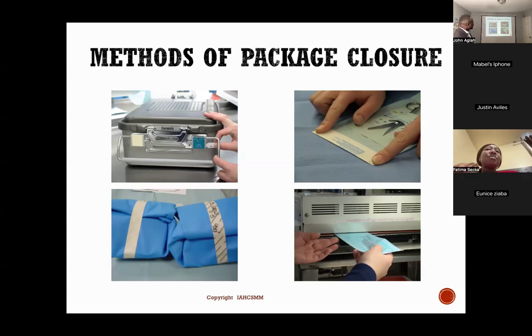So with the heat sealer, when you go to your workplace, you turn it on. There's a switch, press it on, and let it sit. As it sits, minute to minute, the temperature rises, so you watch the temperature until it's up to where it's supposed to be. If you seal a peel pouch and the heat sealer isn't up to temperature, it won't seal properly. You'll see the line, but it will open. You want it to seal solid, because this is what prevents bacteria from getting back in to compromise the instrumentation when you store these items. It needs to be sealed properly.